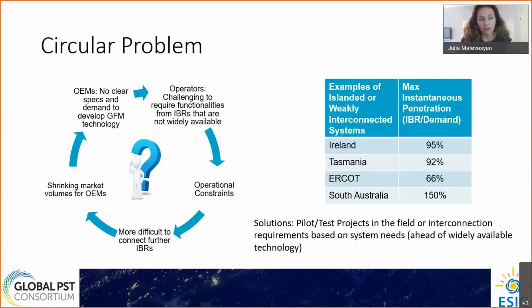This may result in shrinking market volumes for OEMs, and then OEMs don't have clear specifications of what is needed from inverter-based technology for the system operators to provide. And there is no standardization so that OEMs can develop these capabilities. One of the solutions to the circular problem that people are testing in different parts of the world is these pilots or test projects in the field. Another angle that I think people are approaching this problem from right now is developing minimum specifications for grid-forming inverter-based resources, to get to the capabilities that are needed for a system with a high share of IBRs.